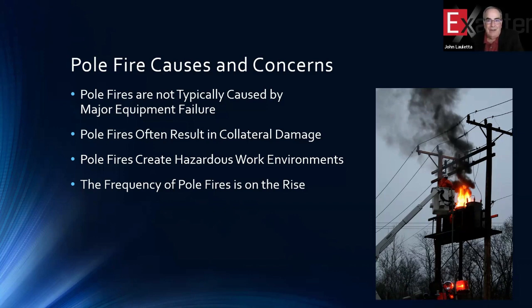We've looked at pole fires from a historical standpoint, and typically you would say that a pole fire itself will generally cause collateral damage. And that's a very expensive proposition for any electric utility because it means that you have to be involved with public relations, maybe litigation, and so on as a result of the event occurring. They certainly create hazardous work environments because now you've got your linemen in a bad situation. You've got firemen involved who aren't as adept at working around electrical situations, particularly when the conductors are live.